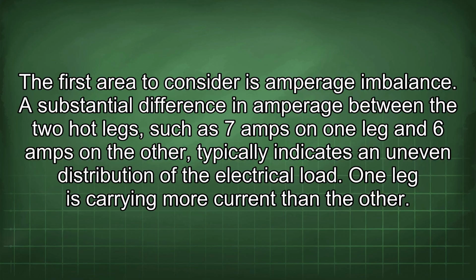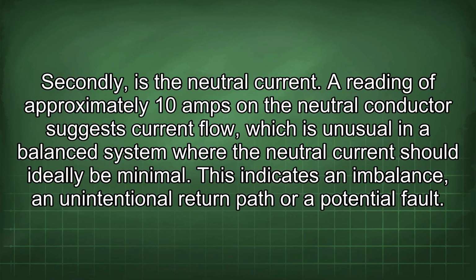A substantial difference in amperage between the two hot legs, such as 7 amps on one leg and 6 amps on the other, typically indicates an uneven distribution of the electrical load. One leg is carrying more current than the other. Secondly is the neutral current. A reading of approximately 10 amps on the neutral conductor suggests current flow, which is unusual in a balanced system where the neutral current should ideally be minimal. This indicates an imbalance, an unintentional return path, or a potential fault.